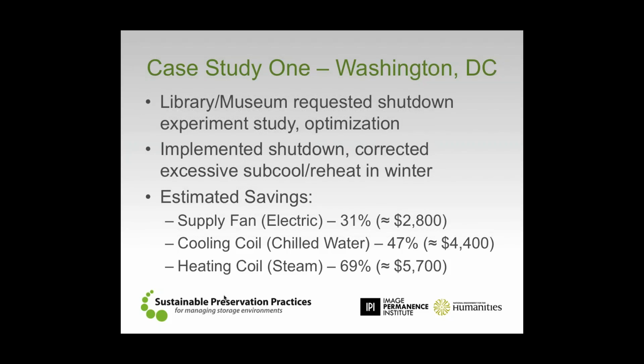You know, we were able to save 31% at the supply fan in terms of how much energy the fan was using, 47% of the total energy used at the cooling coil, and 69% of the energy used at the heating coil. Notice that the actual dollar amounts look pretty small. And that's something that I want to caution you about as you start going in and thinking about this, is that this is not always a get-rich-quick scenario. This is something where you're trying to do a better job of it, and you're trying to be more efficient. And oftentimes, if you're working with a relatively small air handler in terms of the amount of air, cubic feet of air that it moves around, then the dollar numbers that you're looking at when you start achieving these savings aren't going to be huge. But the percentages are meaningful, and the lessons that we learned from this are really significant.